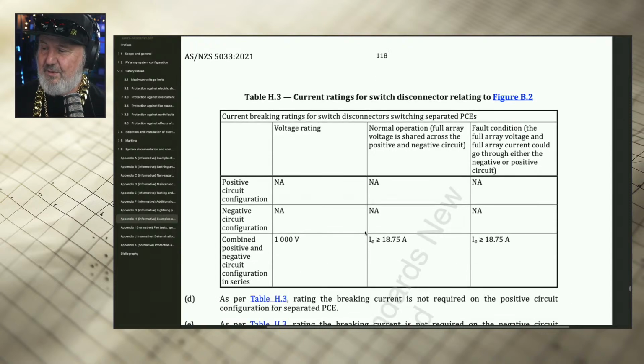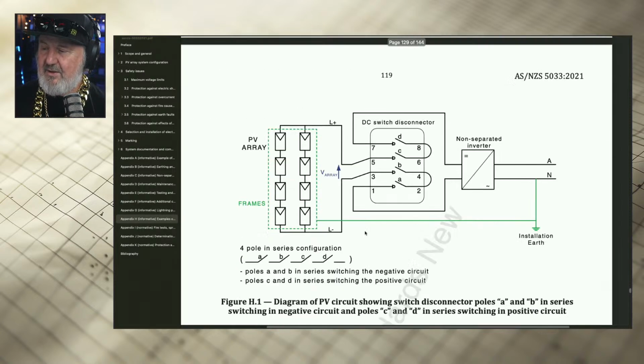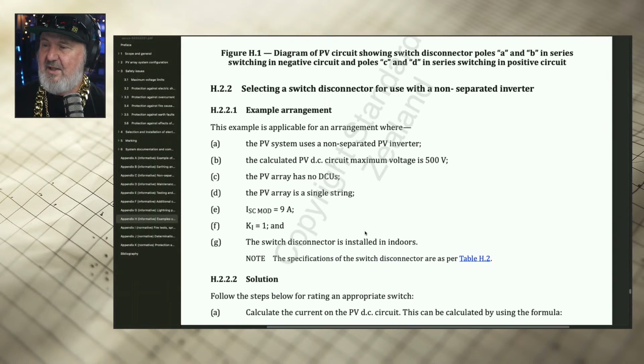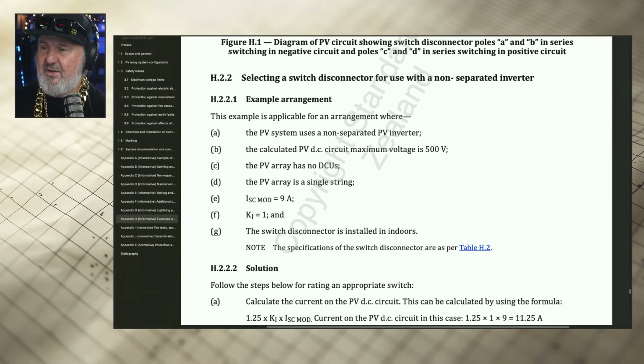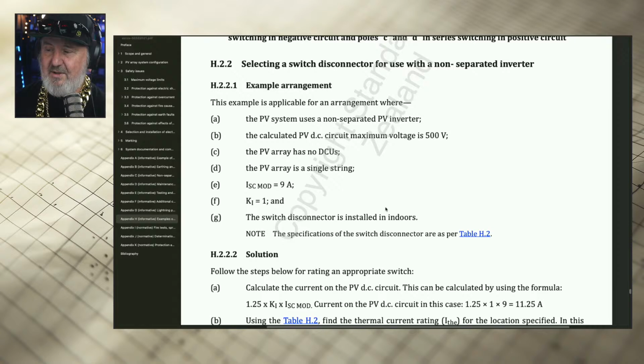Now let's look for a non-separated inverter. So here we go. Selecting a switch disconnector to use with a non-separated inverter, and we've got here a 500 volt open circuit. So it's not as high as previously, so it's only 500 volts open circuit, and there are no DCUs, as we explained before, and the PV array has only one string. So the ISC of a module is also the ISC of the string, but we've got to apply the K factor, which is 1 because they're not bifacial, and the 1.25 times safety margin.